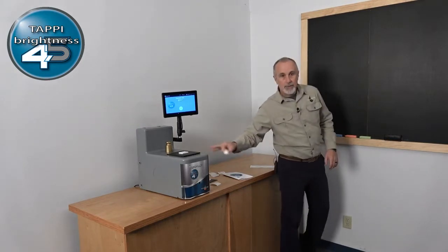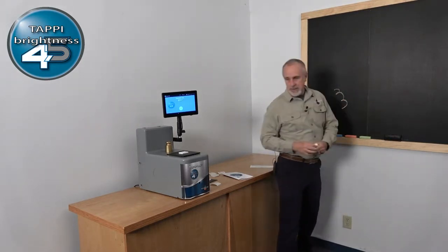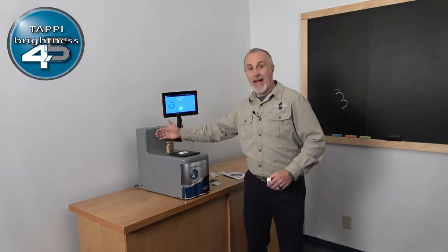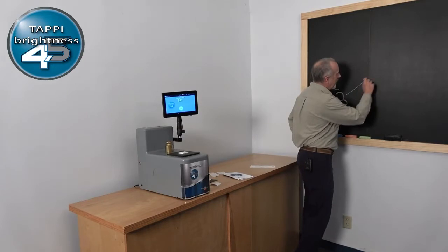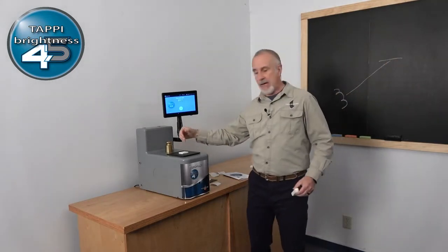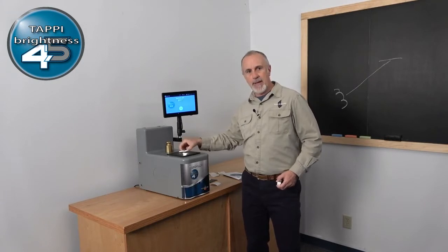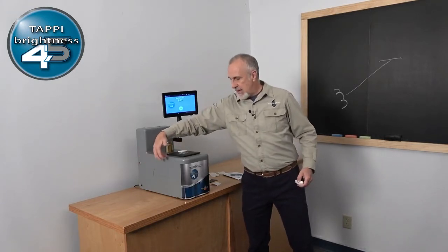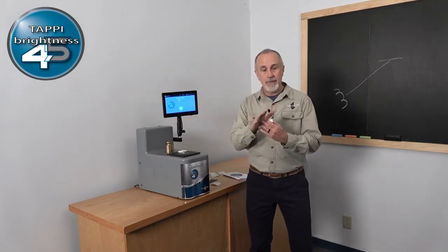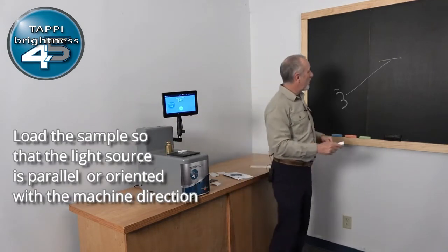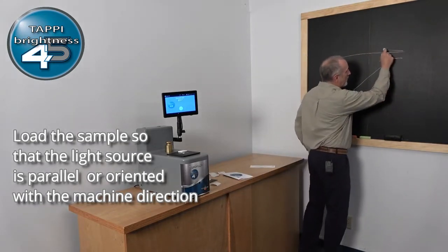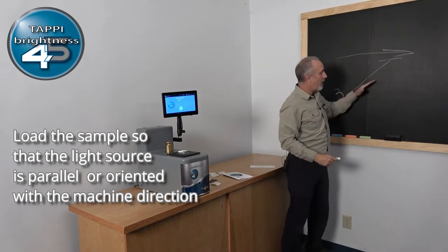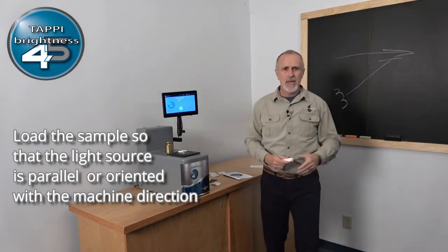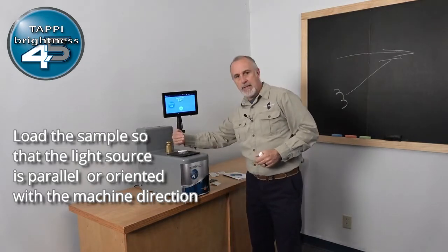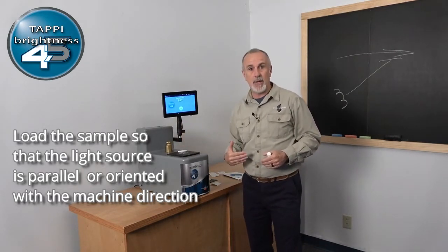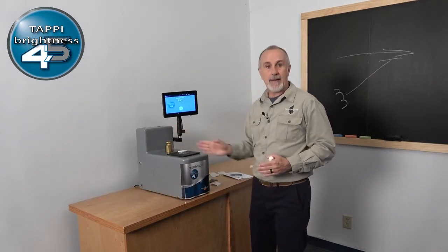So in a directional brightness instrument like this, you've got a light source which sits right here against this back wall, if you will. That light illuminates the sample plate here. You can see there's a little bit of light coming out of that. So you have a light source and it's directionally illuminating the sample at a 45-degree angle. With that being the case, what we want to make sure is that our machine direction, or the fiber direction, is in parallel with the sample. So when you load that sample, you want to make sure that the machine direction is just like this as well. Machine direction runs front to back of the instrument.